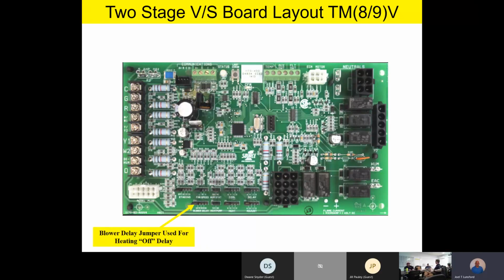Down below that, we have a blower delay, and this is used for heating off delay. Now remember, once the call for heating goes away, your furnace is going to continue to run a little bit to cool the heat exchanger down and to distribute whatever residual heat you have on the heat exchanger into the conditioned space. How long that blower runs after the call for heat goes away is determined by this jumper. You'll notice if you look at it closely, it's 60 to 180 seconds. We typically ship it at about 120 seconds, a 2-minute off delay. But you can go up to 180 seconds, a 3-minute off delay, or down to a minimum of 60 seconds for a 1-minute off delay.